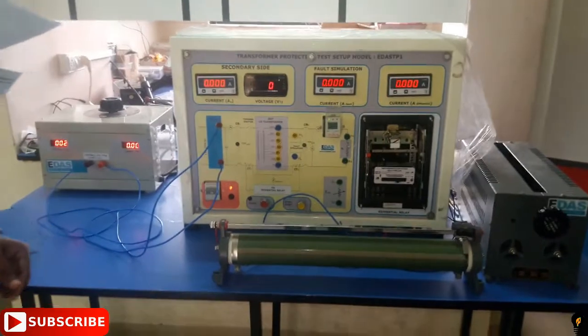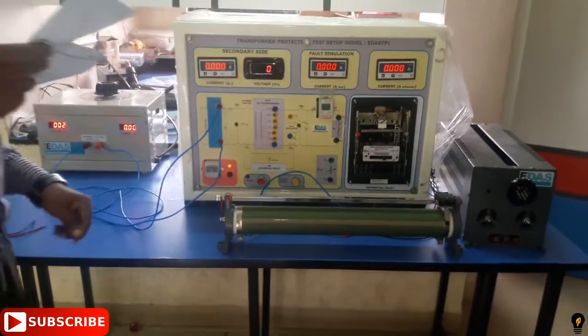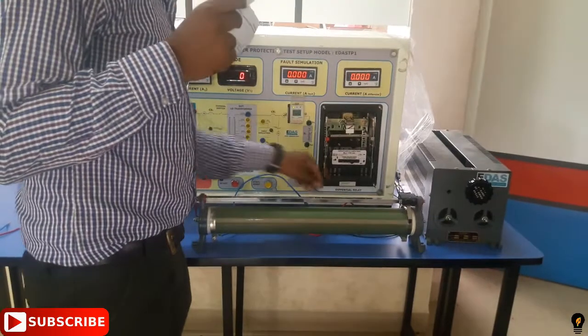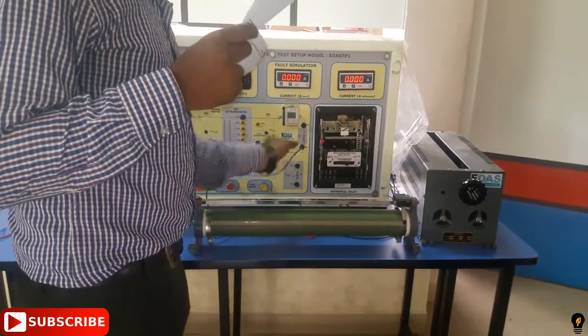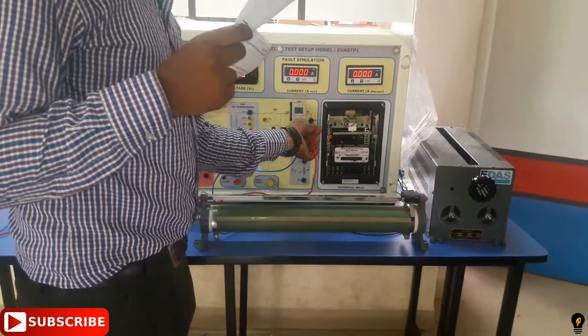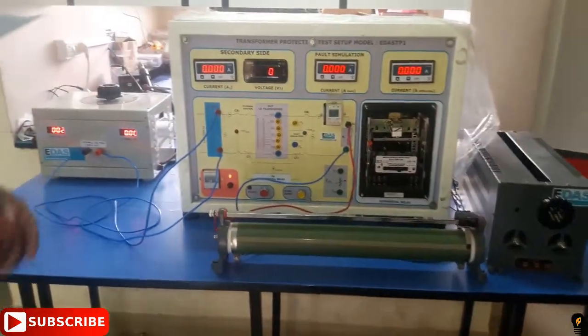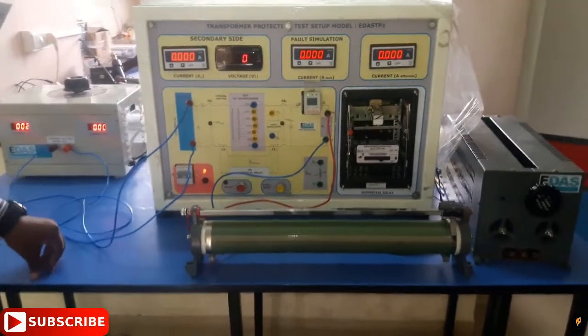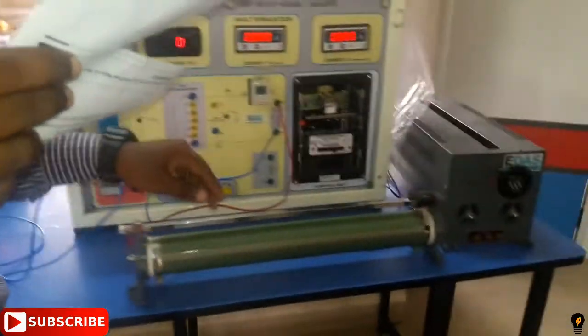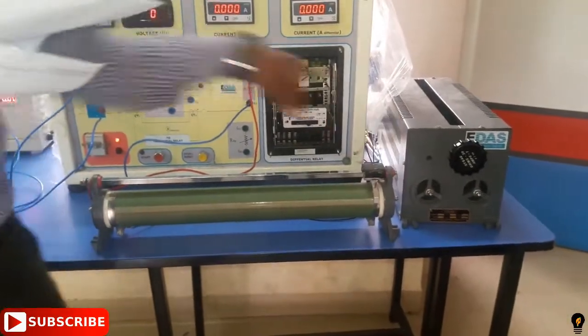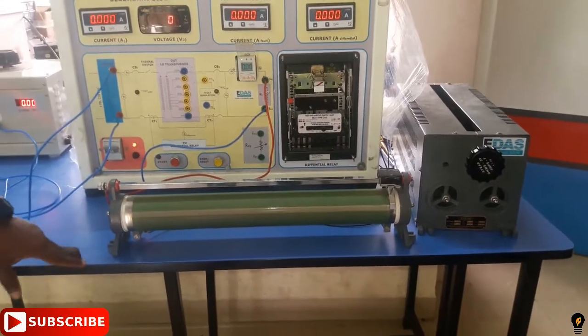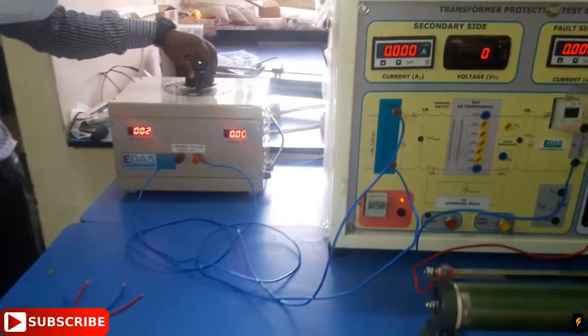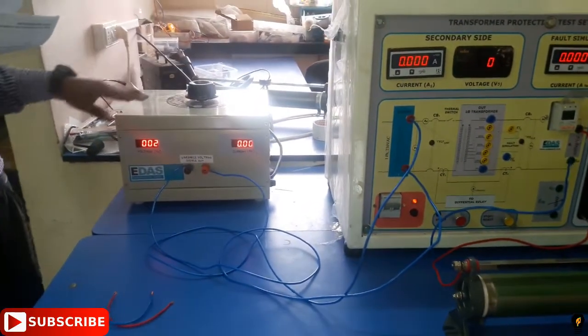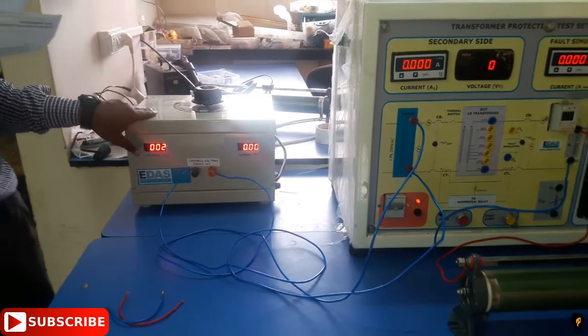Then connect external load to the RL1 and RL2 terminals of the transformer protection test setup. These are the RL1 and RL2 terminals of the load rails. Make sure that the variable terminal of the rheostat is at maximum position. This is the maximum position and this is the minimum position. Make sure the knob position of the source unit is in the extreme anti-clockwise direction, meaning your source voltage is at 0, near to 0.